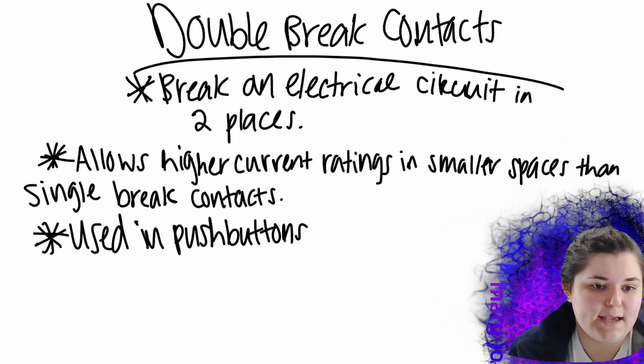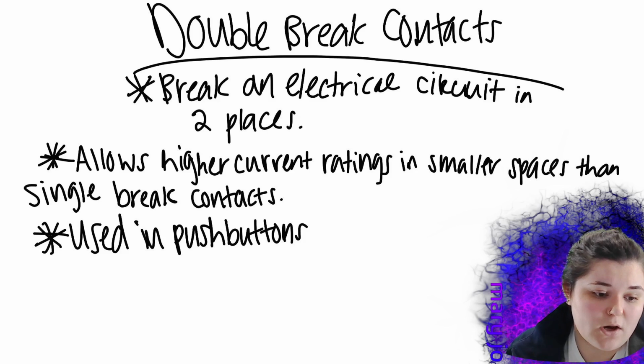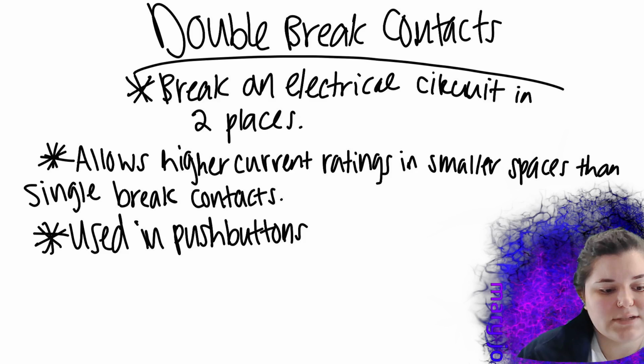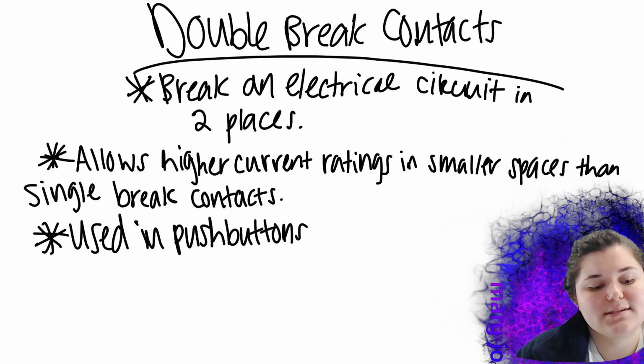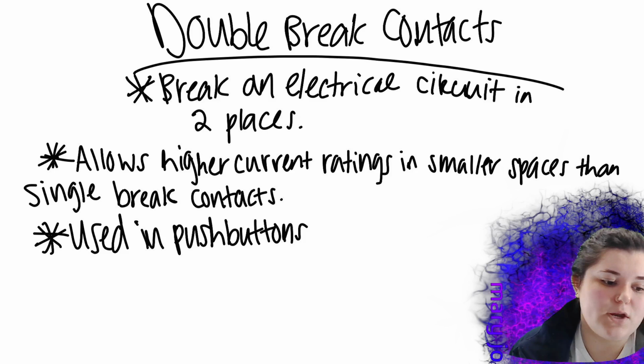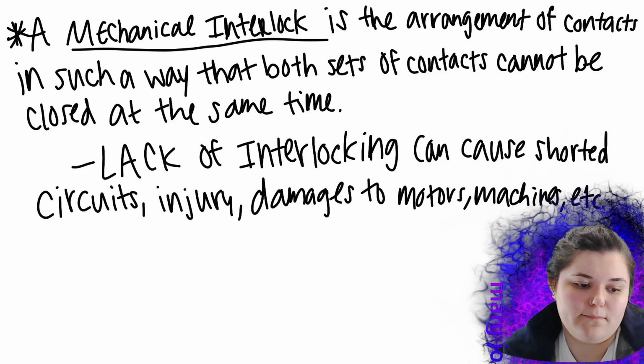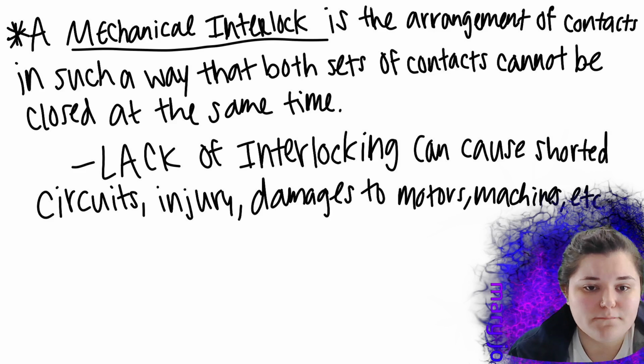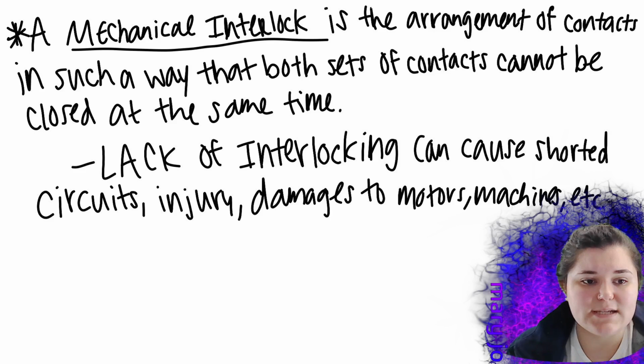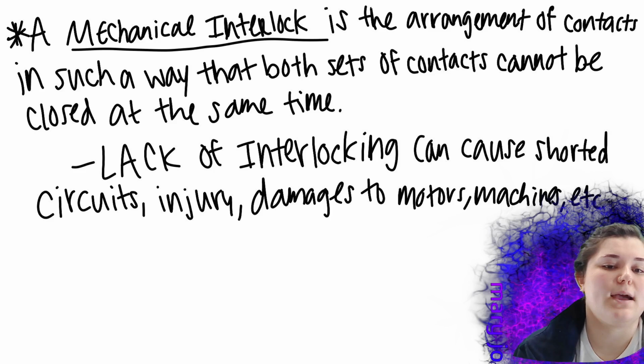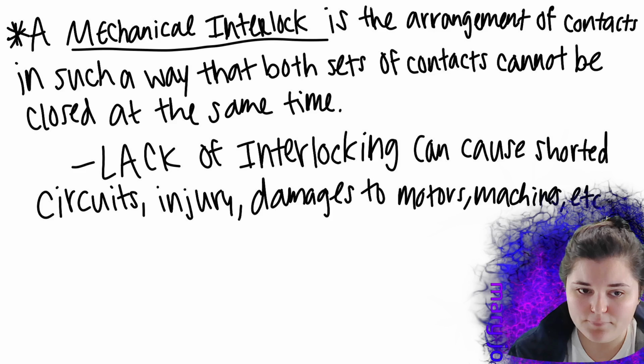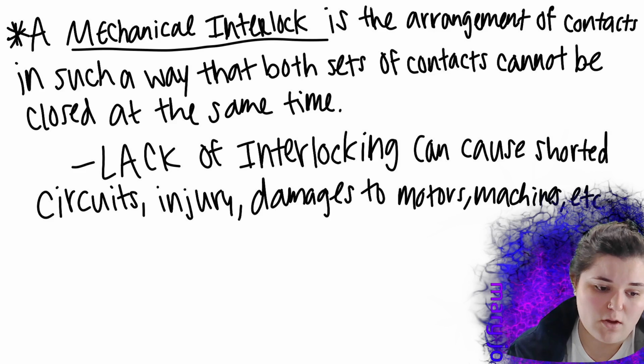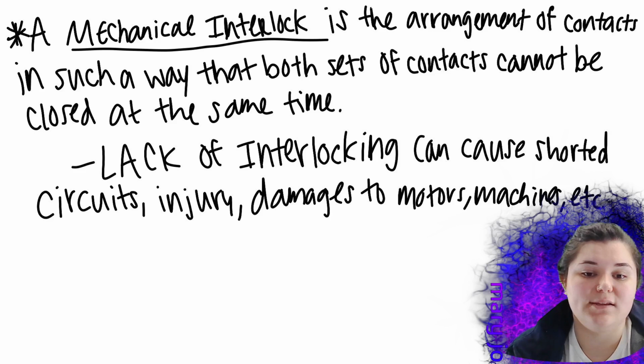Double break contacts. Breaks an electric current in 2 places. Allows higher current ratings in smaller spaces than single break contacts. They're used in push buttons. A mechanical interlock is the arrangement of contacts in such a way that both sets of contacts cannot be closed at the same time. Lack of interlocking can cause shorted circuits, injury, damages to motors, machines, etc.